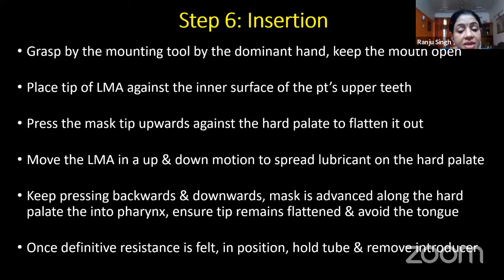Lubricate the hard palate by moving the device in an up and down motion to spread the lubricant on the hard palate. Once this is done, gently slide the device backwards and downwards with a firm pressure. It is moved along the hard palate, following the palatopharyngeal curve, and ensure while doing this that the tip remains flattened and avoids the tongue. Do not push the device towards the tongue side. Always make sure that the device is pushed along the hard palate.